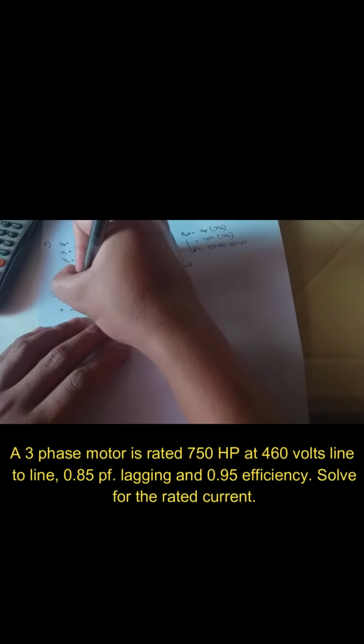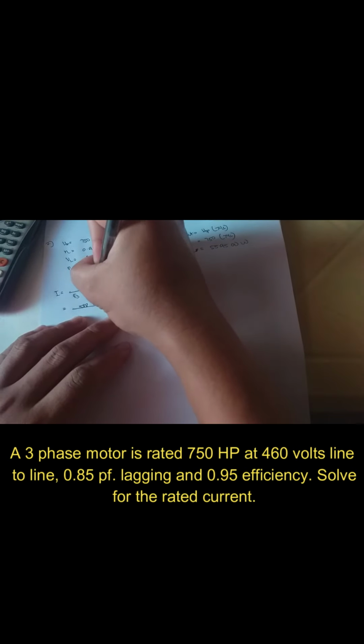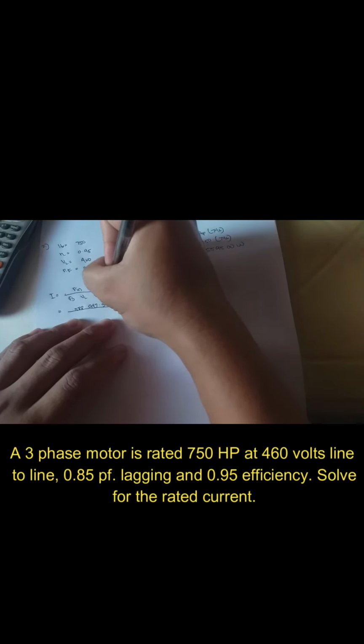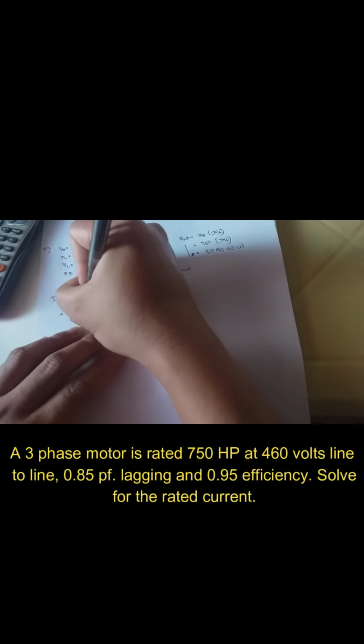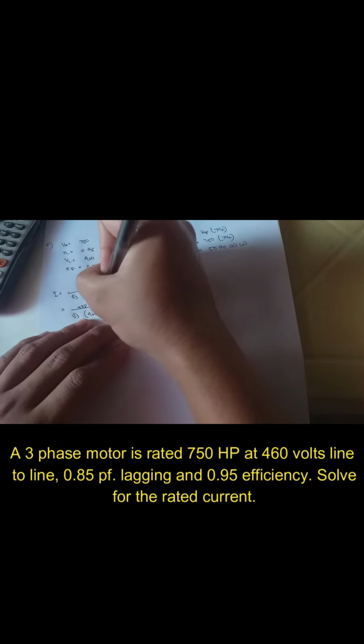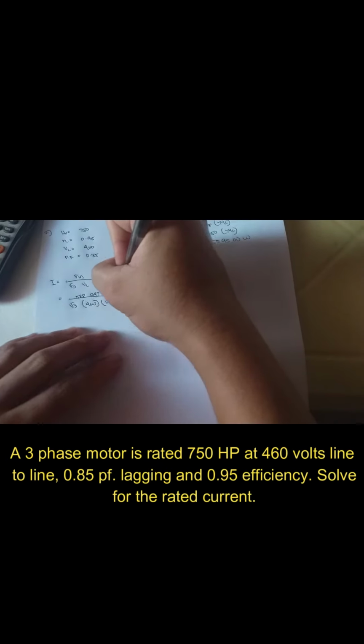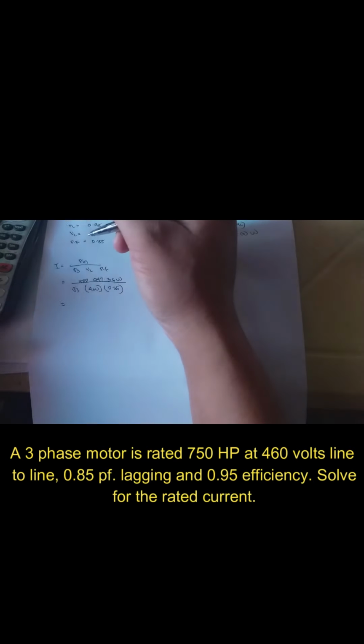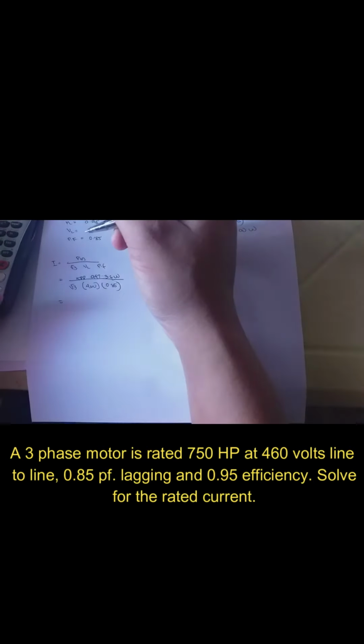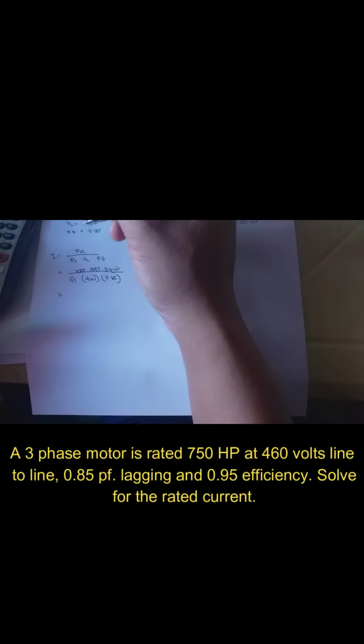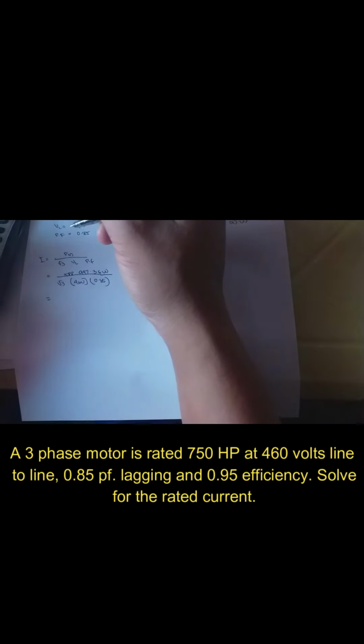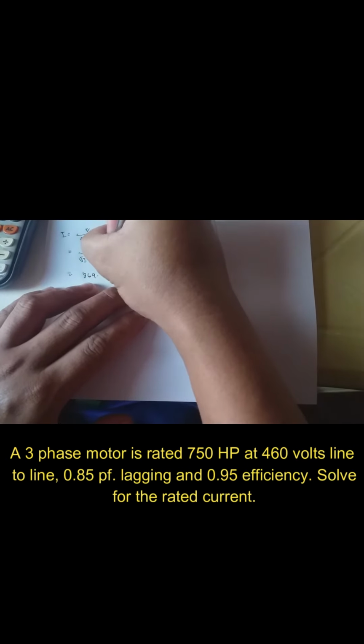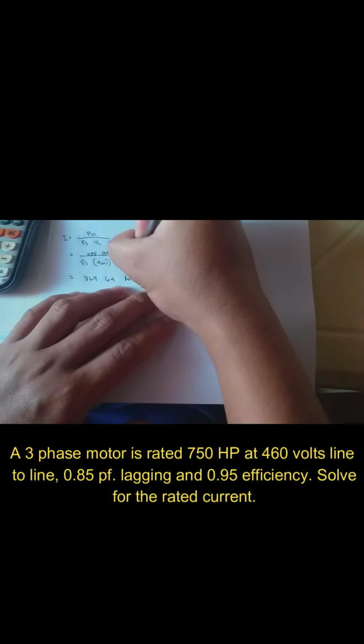Input power is equal to 588,947.36 watts over the square root of 3 times the load voltage of 460 times the power factor of 0.85. 588,947.36 divided by square root of 3 times 460 times 0.85 is equal to 869.64 amperes.